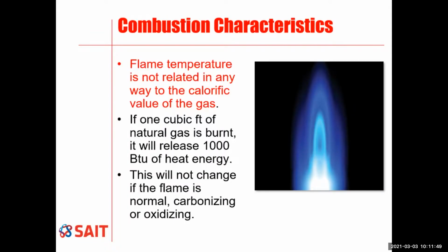Okay, flame temperature is not related in any way to the calorific value. Okay, so don't associate that. So if 1 cubic foot of natural gas is burnt, 1,000 BTUs of heat energy will be released. Okay, this will not change if the flame is normal, carbonizing, or oxidizing. And we should have learned what carbonizing is, and what oxidizing is, comparatively to what flames are. Carbonizing, fuel rich. Oxidizing, oxygen rich. Okay, one or the other.